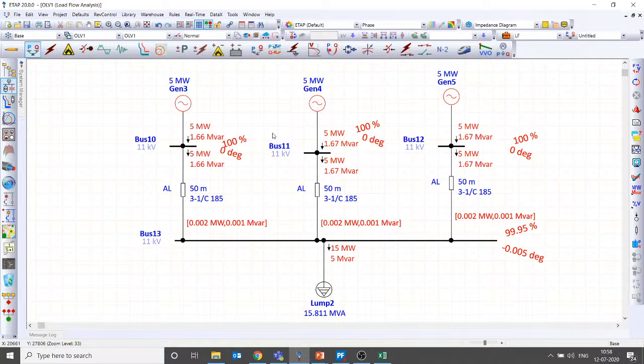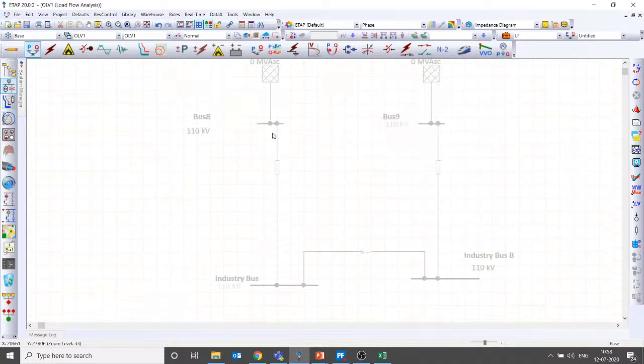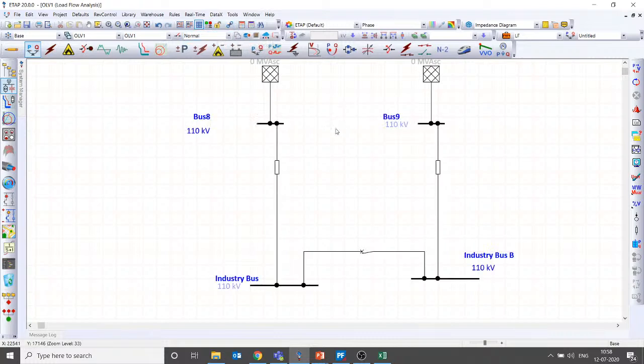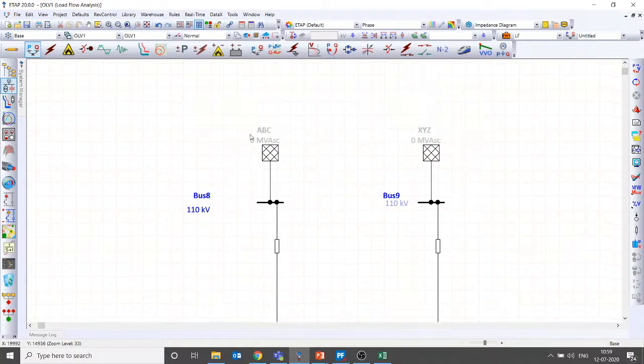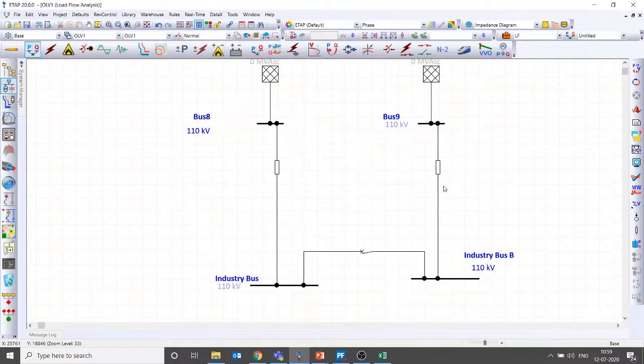There is a question from Vishal Kumar. When a substation receives two sources, is it the same case as two grid sources with a tie bus? Then how are we controlling kilowatt and kVAR power flows? Vishal Kumar, I think you might have confused this with the previous example. To showcase, I will switch on the circuit continuity. If I have a double circuit from the same common bus, that means bus 8 and bus 9 are not two different buses. If bus 8 and bus 9 are the same bus, that means this is not substation ABC and substation XYZ, then it's a double circuit line which you can parallel.